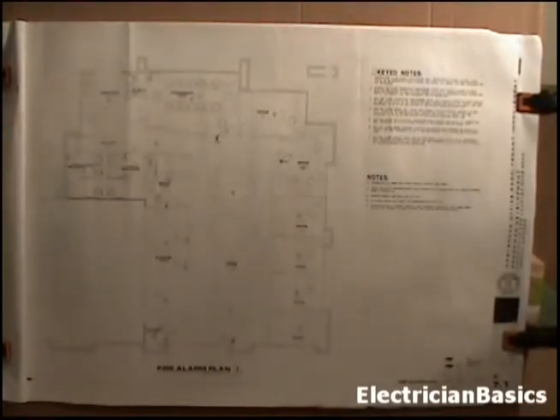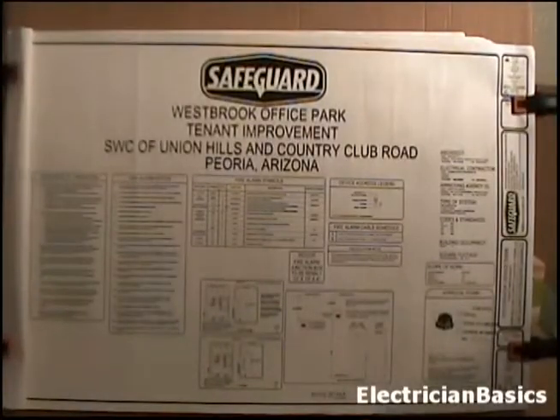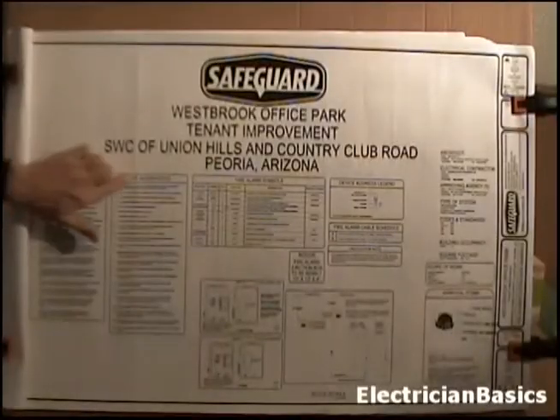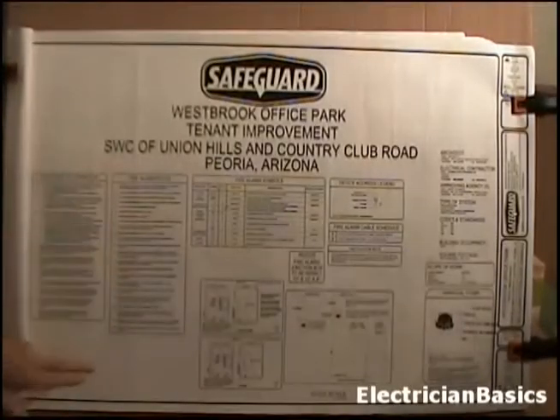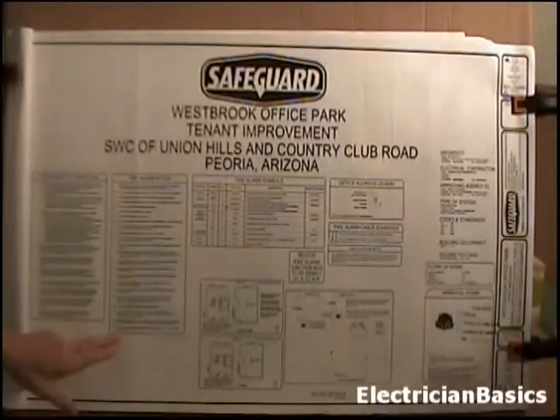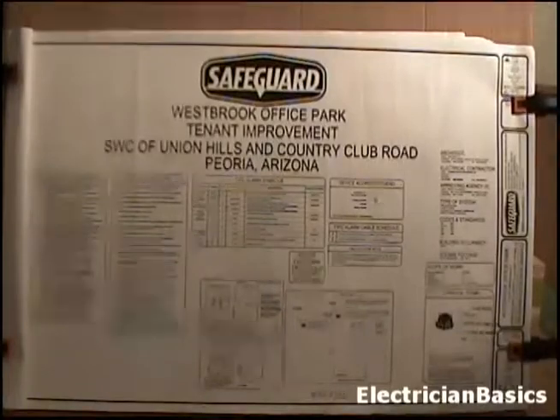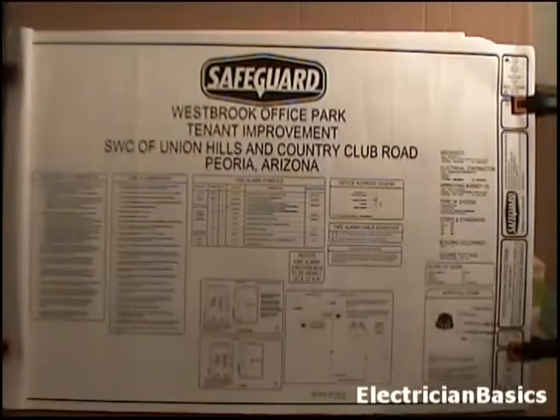Now we look at that note and we have a pull station, but how high should we mount that pull station? In order to find that on this set of blueprints, we need to turn forward a few sheets to sheet FA01. So let's do that right now. Here we are at sheet FA01, and it's the fire alarm device details. This is the fire alarm notes right here, and I just want to point out note 23 down here. It says pull station shall be mounted no more than 48 inches above finished floor to the top of pull station.